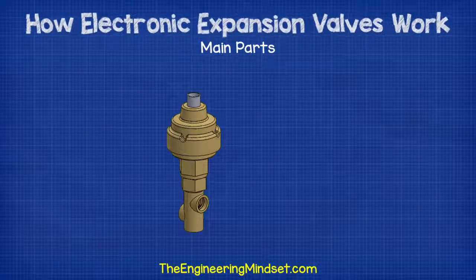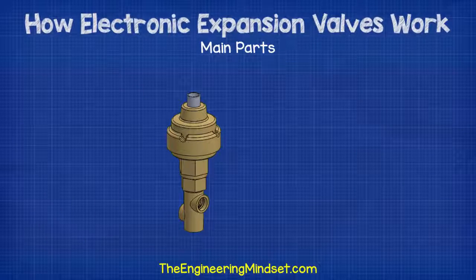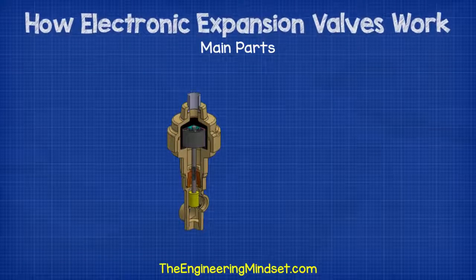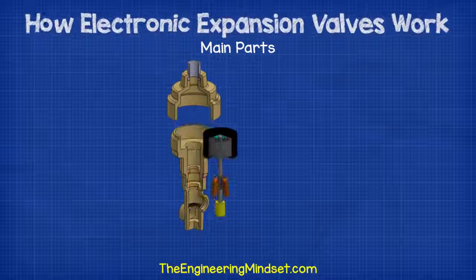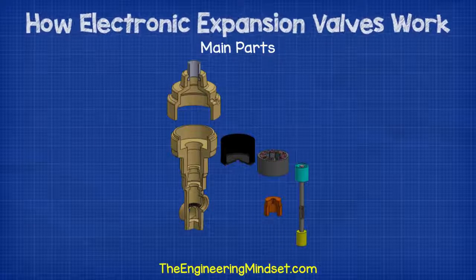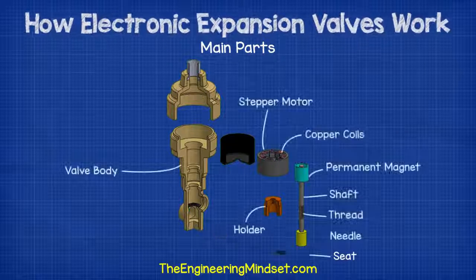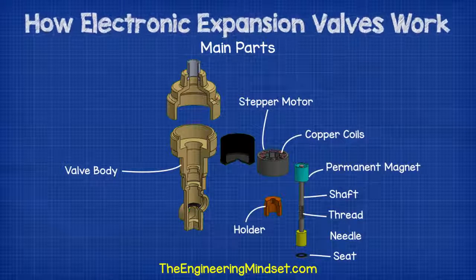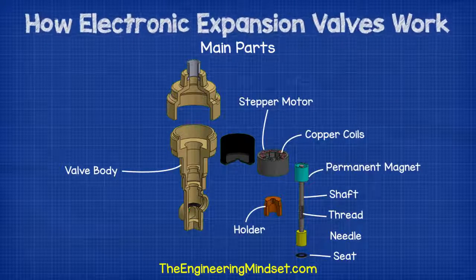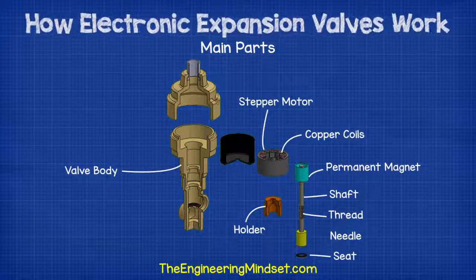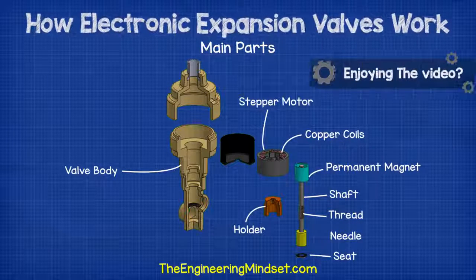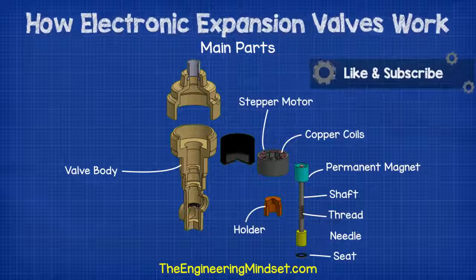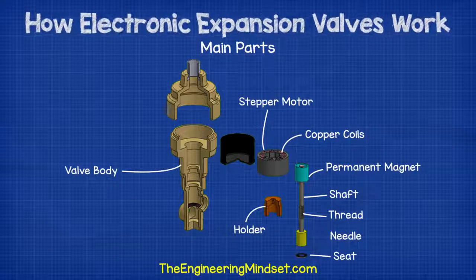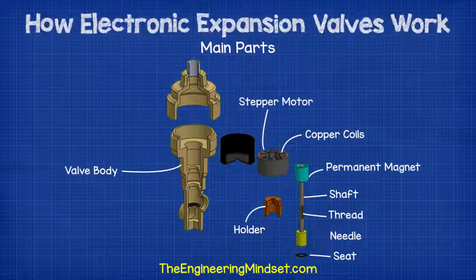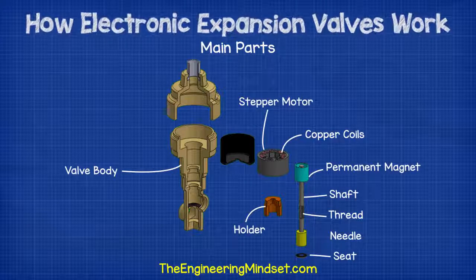Main parts of the electronic expansion valve. As we just saw, there are many different designs for electronic expansion valves, but we're going to focus on a simplified design to help build your base knowledge. This design uses a permanent magnet stepper motor. At the head of the valve, we have the stepper motor body, which contains the copper coils. These are used to generate an electromagnetic field, which will be used to control the valve's position. Sitting concentrically within the main body of the stepper motor is a permanent magnet. This permanent magnet is affected by the electromagnetic field of the coils, and the change in polarity of the electromagnetic field will cause the permanent magnet to rotate.